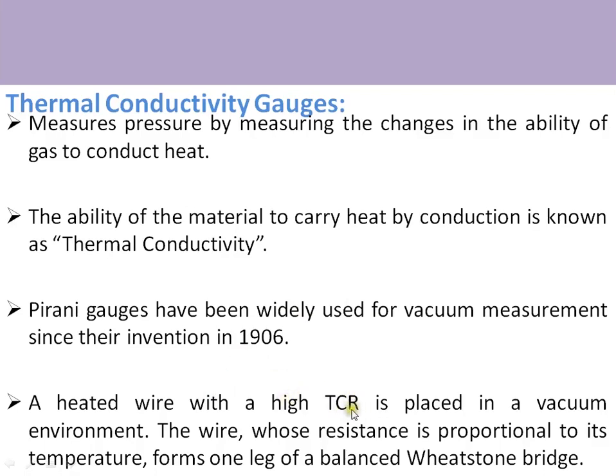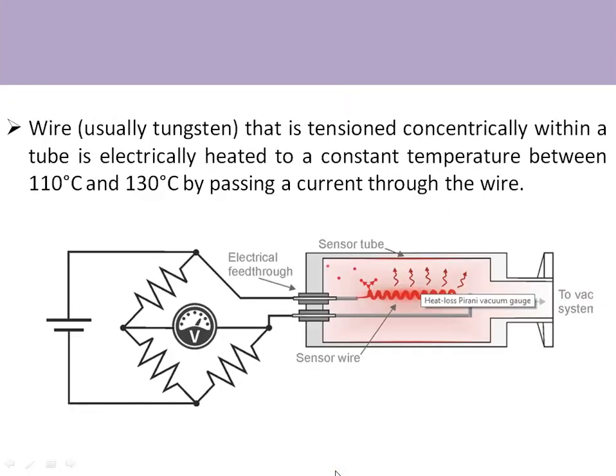In thermal conductivity gauges — the Pirani gauge — a heated wire with a high temperature coefficient of resistance, made of tungsten, is placed in a vacuum environment. The wire's resistance is proportional to temperature and forms one arm of a Wheatstone bridge. The Pirani gauge head contains a tungsten filament forming one arm of the bridge, connected to the system where vacuum is to be measured. More molecules means higher pressure, which means more heat is carried away, causing temperature and resistance of the filament to decrease.